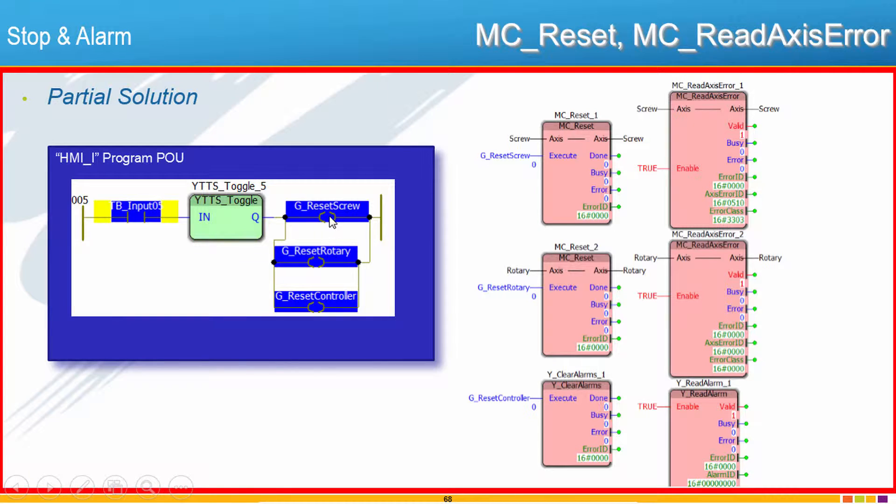The HMI POU has coils to reset the screw, the rotary and the controller. So there's the two real axes and the controller. PLCopen covers reading and resetting the axes, and those are the MC Reset, MC Read Axis Error. Again very simple blocks. You just give it the axis and tell it whether it should execute the reset, or whether it should enable the reading of the error. We'll typically set that to True if you just want that to constantly read the error.